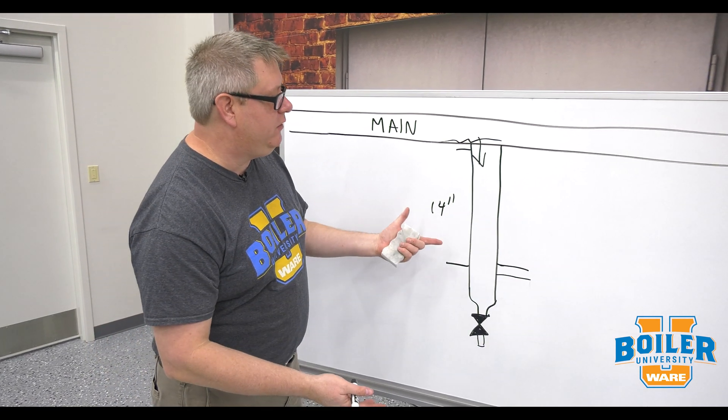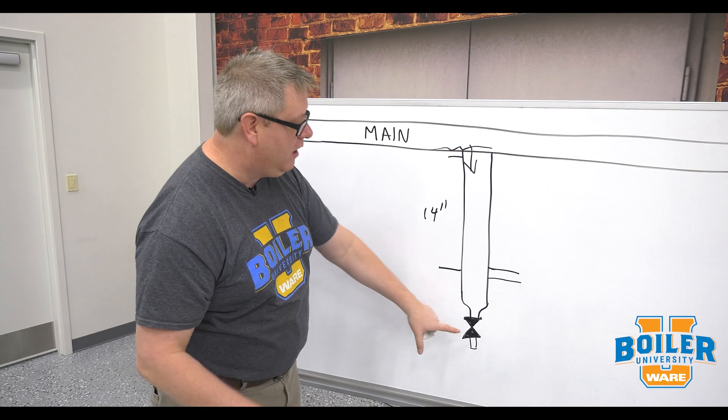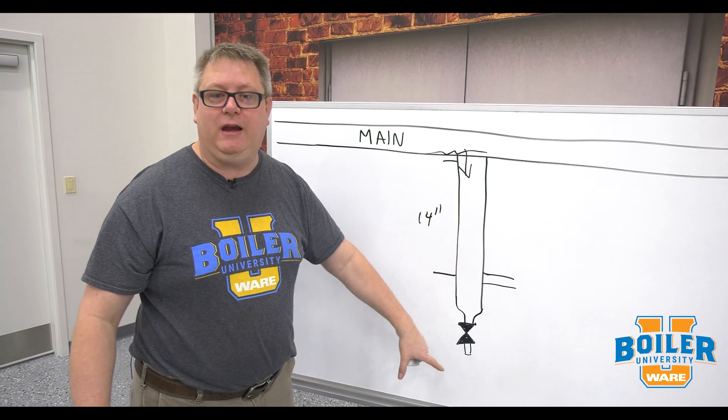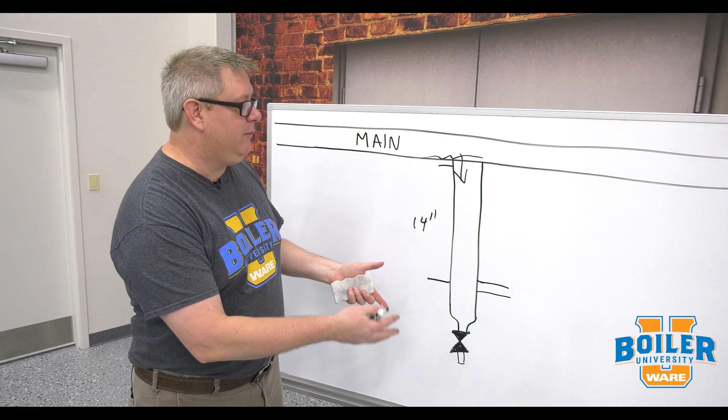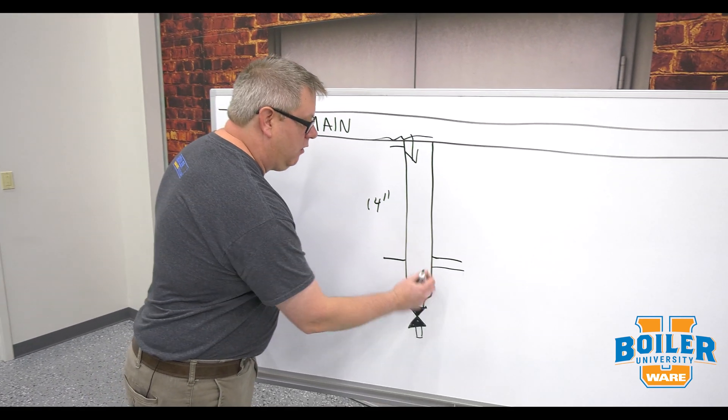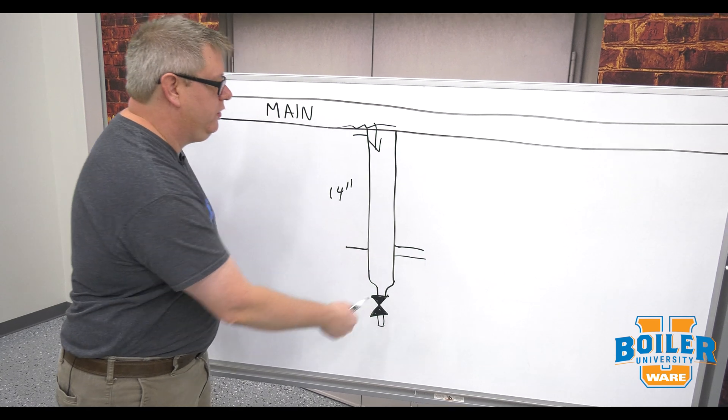A manual start up on a system means when I shut the system down I may go around and open these drain valves to remove, allow condensate to drain from the system and as the system comes back up I will, when steam starts coming out, close those.